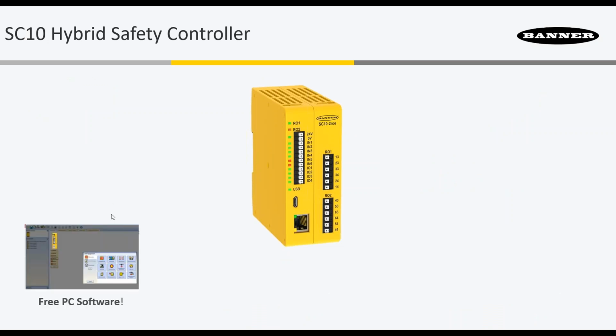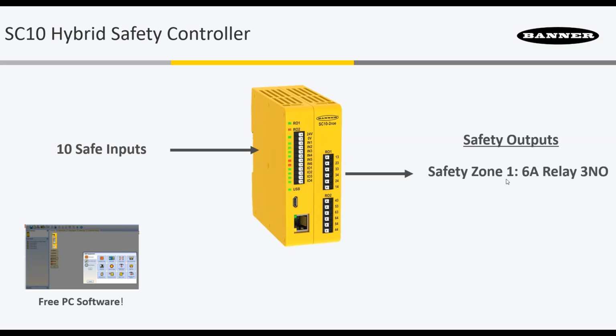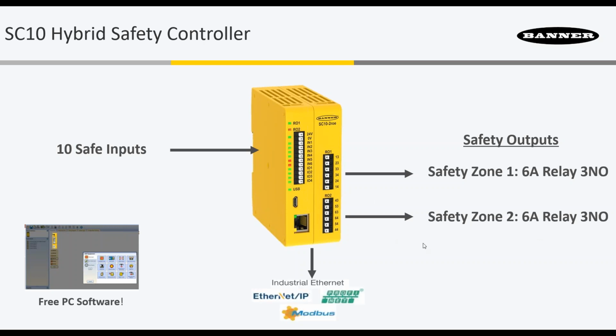So what this product is, again, it uses that same free PC software to configure your inputs, your outputs, your logic. It has 10 safe inputs. And for the safety outputs, you've got your safety zone 1, that's a 6 amp relay with 3 sets of normally open contacts, and an independent safety zone 2 that's also 6 amps and also has 3 normally open sets of contacts. And it has industrial Ethernet, so it's smart. It can do diagnostics. It can receive virtual inputs for resets.